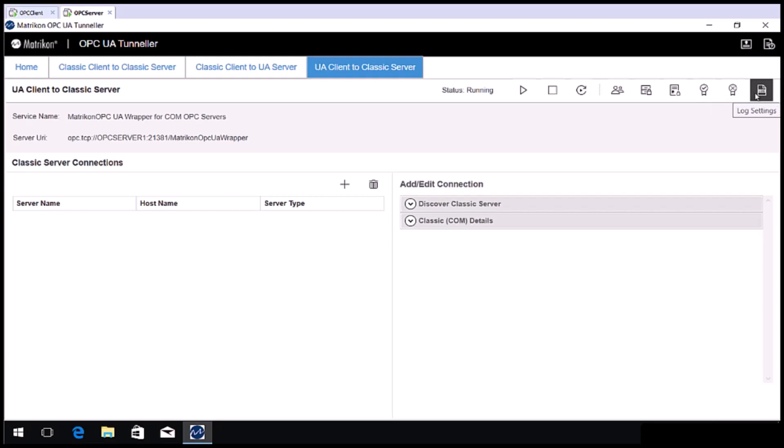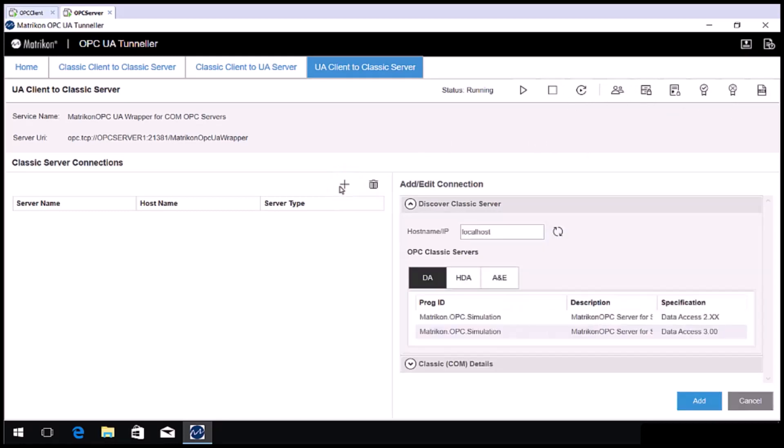Let's go ahead and configure a connection. Click the plus sign. In most cases, we recommend you install the Matrikon OPC UA Tunneler on the same computer as the classic OPC server to avoid DCOM issues. In this example, we will connect to the Matrikon OPC server for simulation on the local host. Select Matrikon.OPC.Simulation under the DA category.